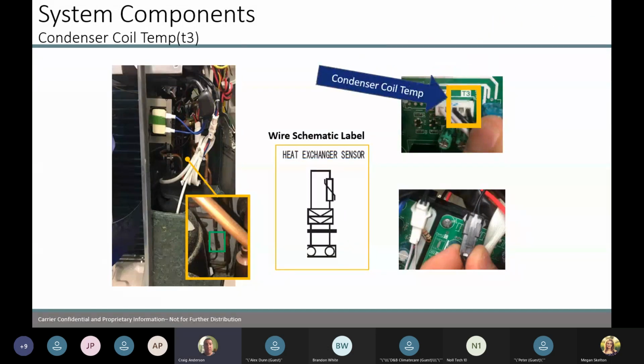Condenser coil temperature. That's another one. It's in behind the compressor. It's on the condensing coil. All this sensor is doing is telling the unit to go into a defrost, or it's time to get out of a defrost. That is all it's doing. As long as it's on that pipe and secure, then we're good to go.